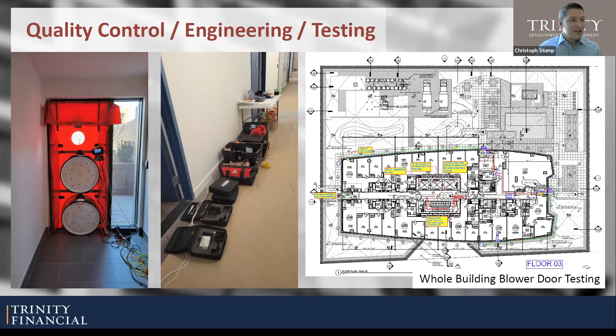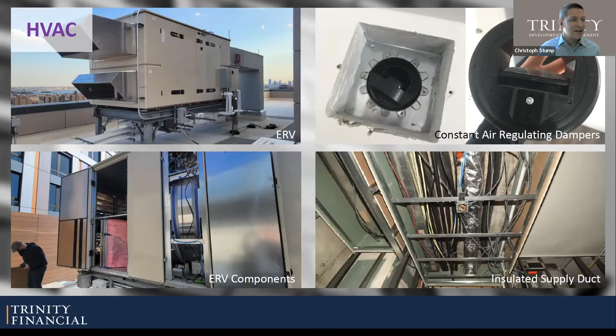The third category is my favorite one, HVAC, and I'm showing some pictures about ventilation. We'll start with that. On the top left, this is an energy recovery ventilator, an ERV. It's a huge, largely empty box, and you see there's two ducts and two grills here on the outside. This is the box where exhaust air bypasses, not mixes, bypasses incoming fresh air and transfers thermal energy. On the bottom left is a picture of the innards. You see it's an empty box. On the top, there's a fan that you can't really see. It's one piece of equipment in this box. Bottom left, you see these pink filter fabrics that give you the absolutely clean, fresh air. Those are MERV 13 or at least 13 filters, so they catch a lot.